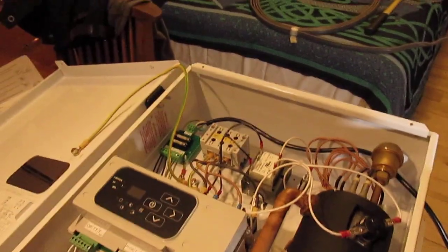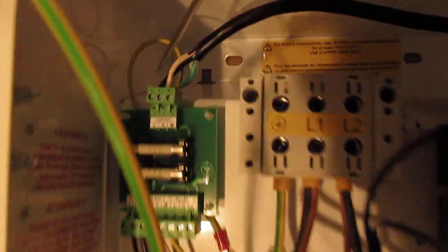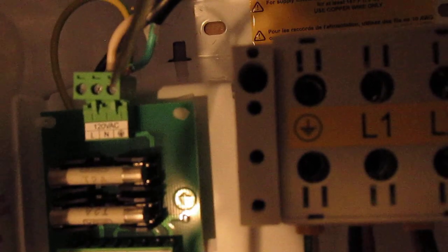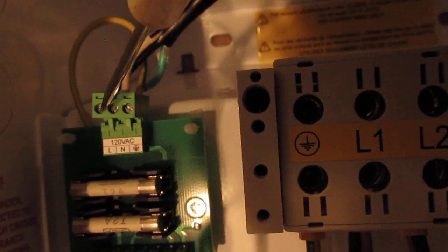So the power is split. You have to have two power sources. So 110 and a 240 volt. The 110 is to run the pump. So I actually just installed a pigtail, you might call it. I bought an extension cord from Home Depot and cut off the end and hooked it up. And the connections are here's a computer right on it. So it's top left of the boiler. A couple of connections down there. This one on the far right, right there with my little screwdriver, that is the ground, the neutral, and the hot wire, the black wire. So that's for the pump.